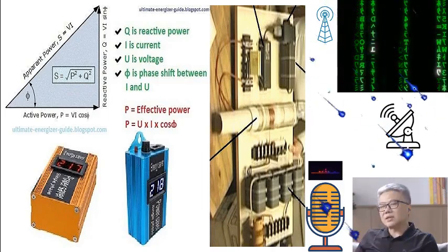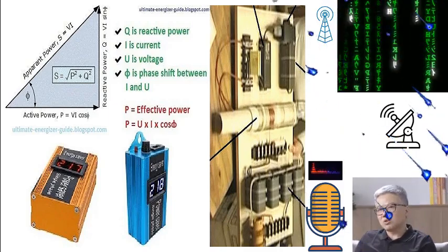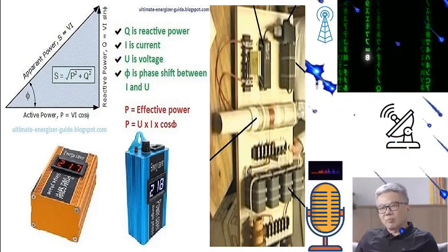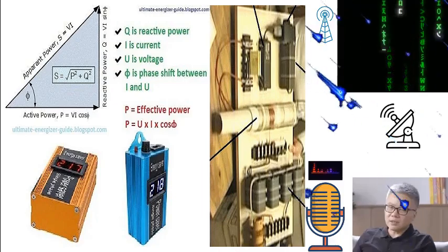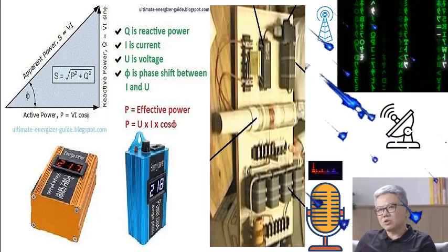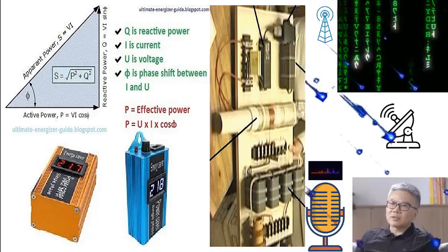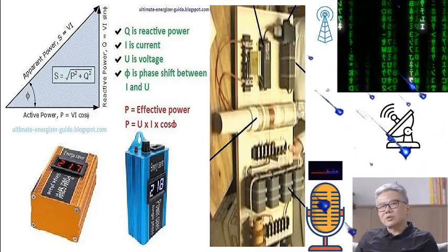Synchronous compensators. These devices operate by using a synchronous motor in no-load mode. They can both generate and absorb reactive power from the grid. Advantages. Synchronous compensators offer dual functionality by either producing or consuming reactive power, making them highly versatile. Disadvantages. They are complex systems with rotating parts, which require careful assembly, regular maintenance, and sophisticated operation. Therefore, they are typically used for centralized compensation with large capacity needs.